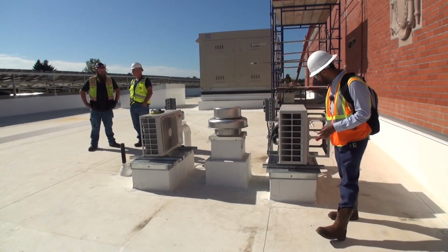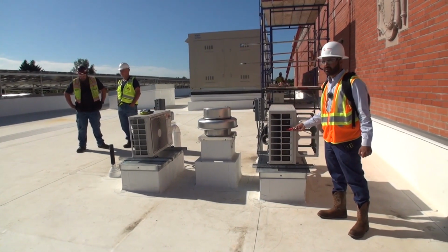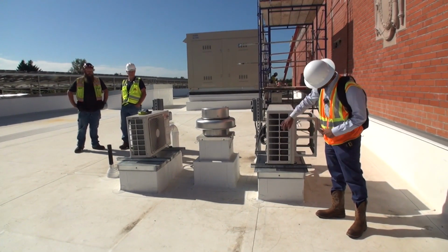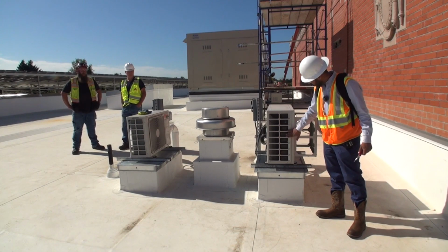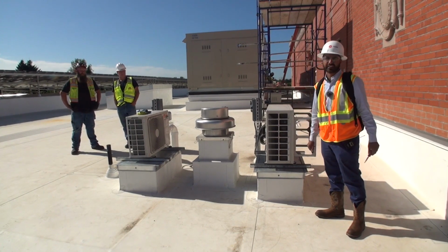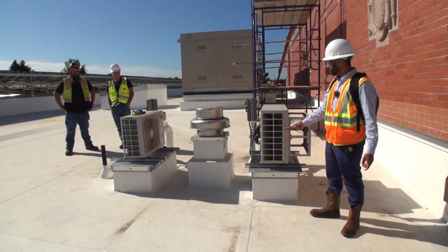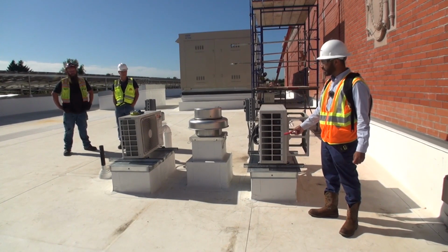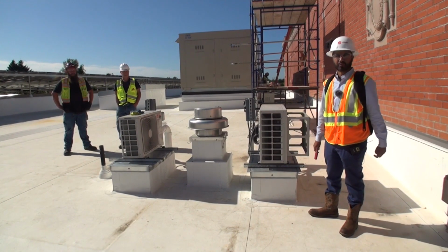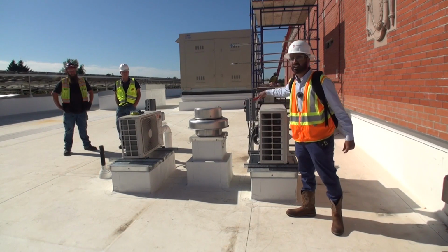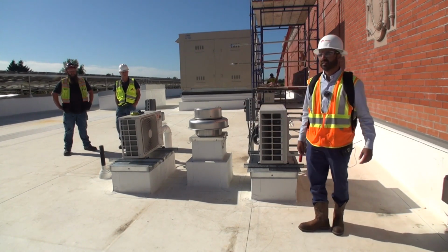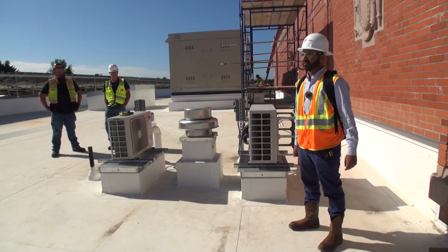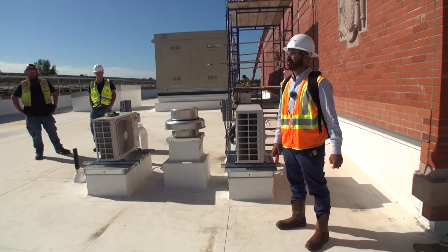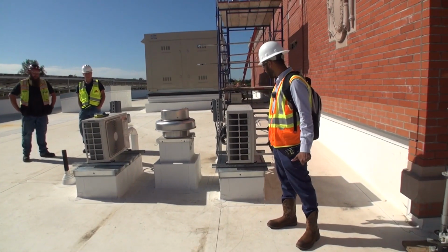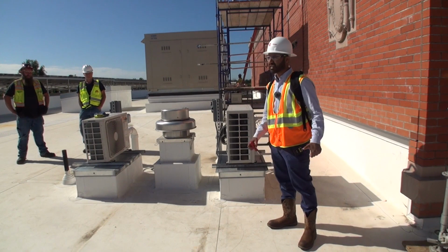Part of what we need to see is also the cleaning we were talking about. You can already see a bit of moss or dust collecting over here. It's not an amount that's really going to affect performance yet, but once it gets all the way across the coil, you're looking at bigger efficiency drops, or not being able to run enough wind across the coils. That could be an issue.